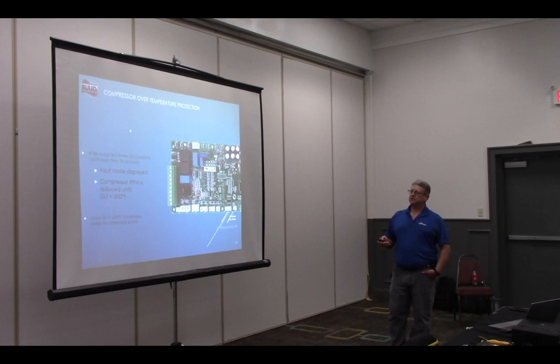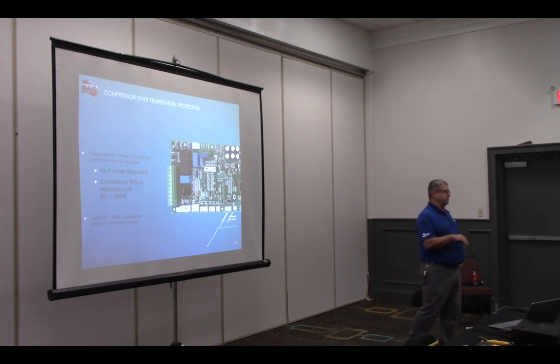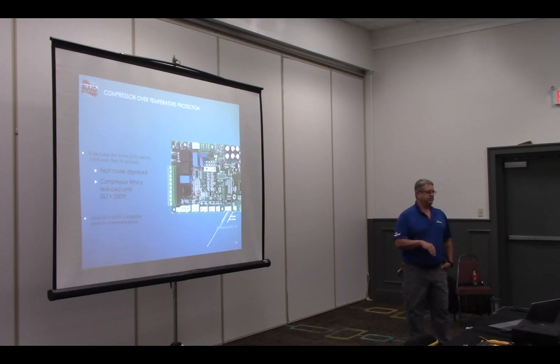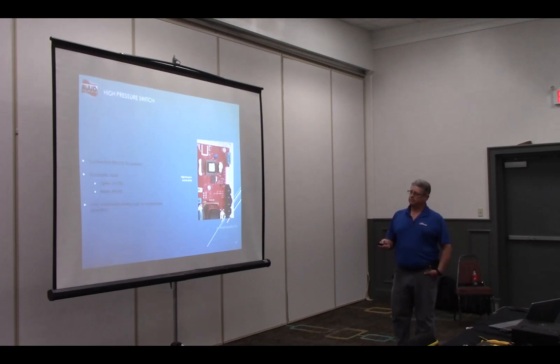If the compressor reaches 235 degrees for more than 30 seconds on a single call, it's going to slow that compressor down, reduce the RPMs until the temperature falls below 200 degrees, and then it will ramp back up. If it does it 3 times in that same call for air conditioning, it's going to lock it out. We have a high pressure switch on here, has an automatic reset, 610 and 490.